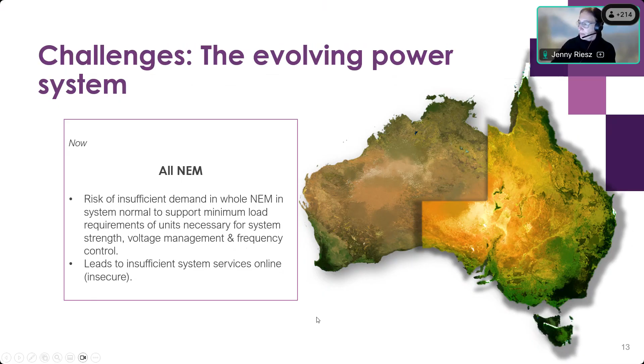To manage these periods, we've introduced what we're calling our minimum system load framework, which is modeled after our framework used in high demand periods, the lack of reserve framework, or LOR framework. The LOR framework is about ensuring there's sufficient generation, and it looks at the potential loss of the two largest sources of electricity to understand as we're approaching system security issues. The MSL framework is the mirror of that, about ensuring that we have sufficient demand, and it manages the potential loss of the two largest loads, which could include an interconnector. So this framework gives a structured way of providing notices to the industry and helping to clear those levels.